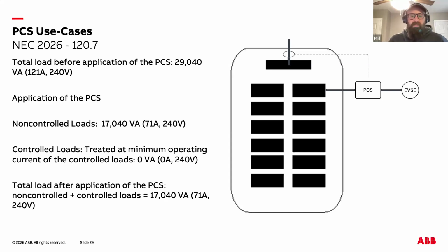In this example, the PCS limit is set at 80 amps, which corresponds to 80% of the 100 ampere OCPD protecting the service, exactly as required by Article 120.7. Because the PCS is monitoring both controlled and non-controlled loads, the NEC requires that the minimum operating current of the controlled load be used in place of its full rating when performing load calculations. Since the EVSE can be reduced to 0 by the PCS, its minimum operating current is 0, and that value is substituted into the calculation rather than the full 50 ampere nameplate rating.